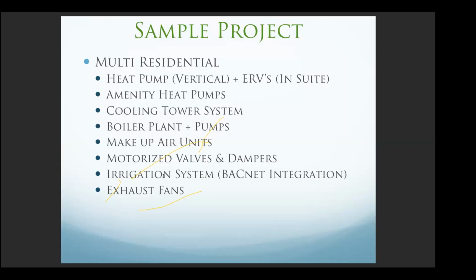In this scenario, there's an irrigation system as well, and it seems like it's coming with BACnet. So what we would do in this scenario is maybe wire up some, and when I say wiring that we do, we as controls contractors, 24 volts is the wiring that we touch. Typically 120 volts is the high voltage, and I know in India it's 240 volts. So the high voltage stuff is done by Division 16, which is the electrical contractor on the job.